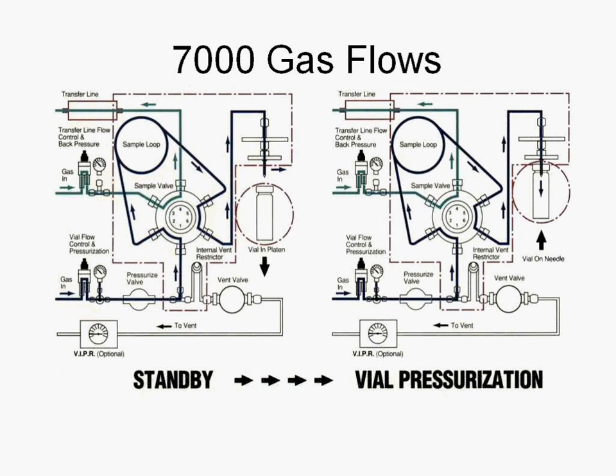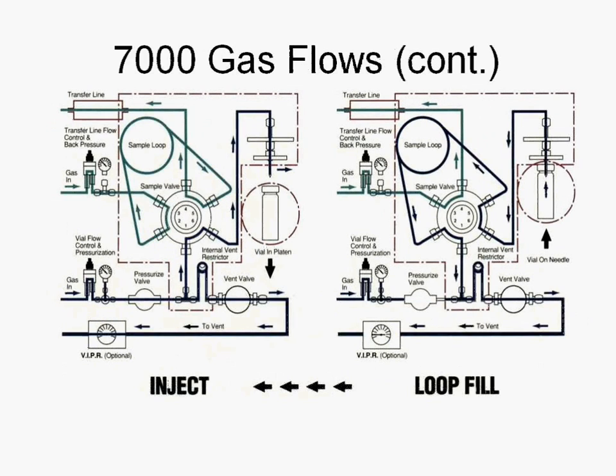During standby flow, our gas comes in, sweeps our sample loop, and comes out our sample needle. You can also see that the carrier line comes in through the six-port valve and goes right back out to our GC. During both the standby and vial pressurization modes, there should be no gas flow coming out of the vent. The only difference between these two modes is when the vial goes up onto the needle to be pressurized. From vial pressurization mode, we go to loop fill mode. There is a burst of flow out the vent during loop fill mode, and then there should be no gas flow.